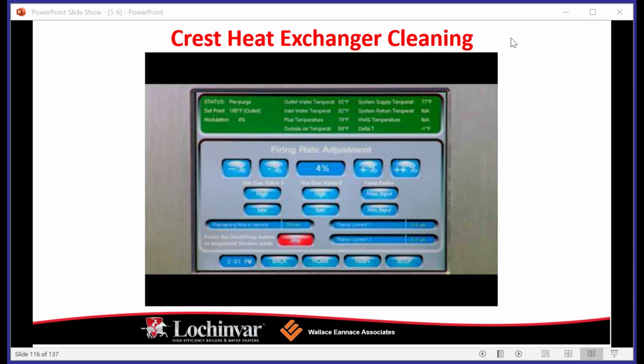Remove the condensate drain line from the condensate trap and route directly to a drain. Rinse out debris from the heat exchanger with a low-pressure water supply. Once the cleaning is completed, reconnect the condensate drain line to the condensate trap. Reinstall the heat exchanger door back onto the heat exchanger.